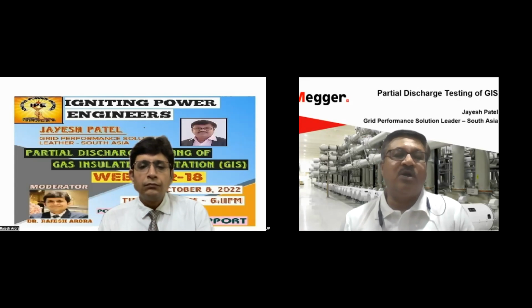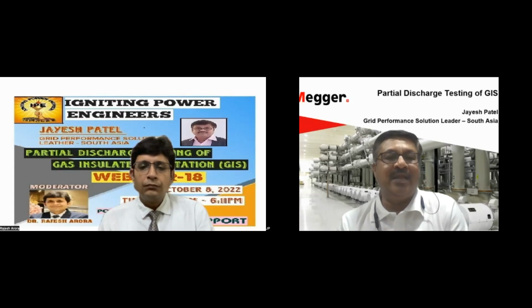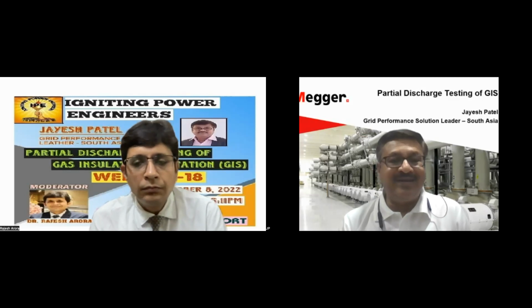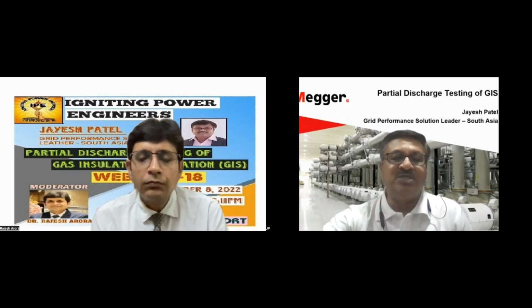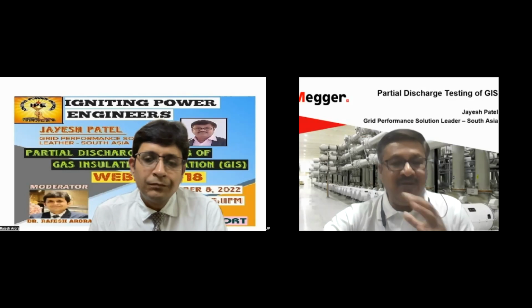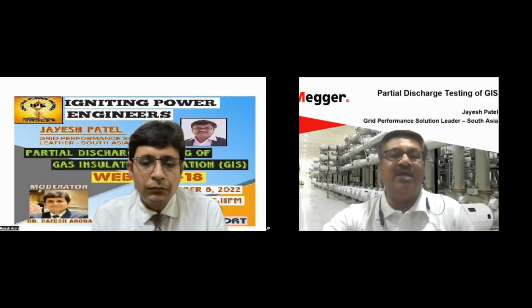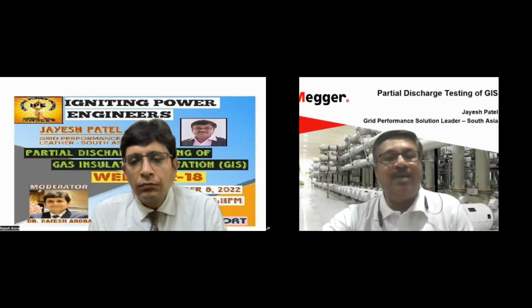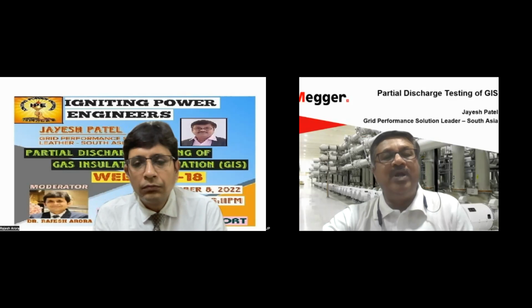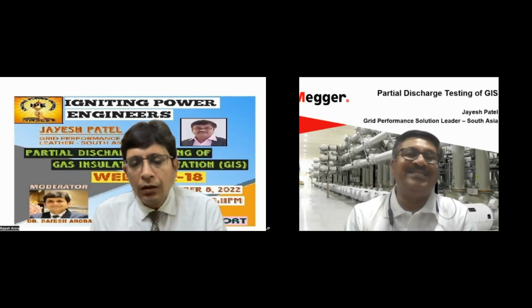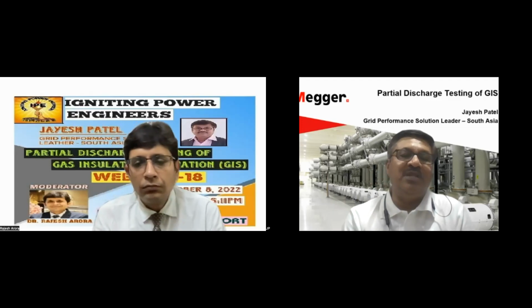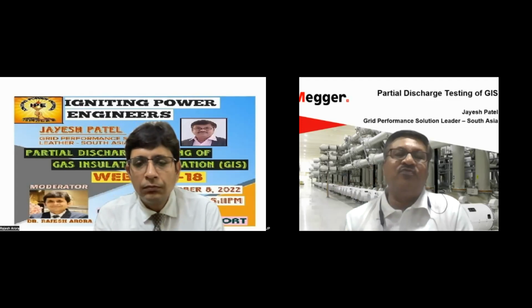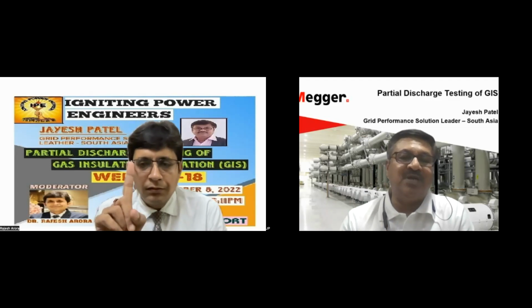But we know that it comes with the cost. If you have multiple assets, or in the same substation you have 3-4 different levels of substations, like 400 by 220 by 110, then you need 3 systems, and it's a fantastic amount of cost which goes in. So people were reluctant to make this kind of investment, but still they wanted some benefit. So we added a facility called remote server into our instrument, and we are providing the same software to our portable device, which is there for the online. So the software is 100% replica. You can use the portable instrument, connect to your GIS, and the software background remains the same. So you can set alarms, you capture PRPD.